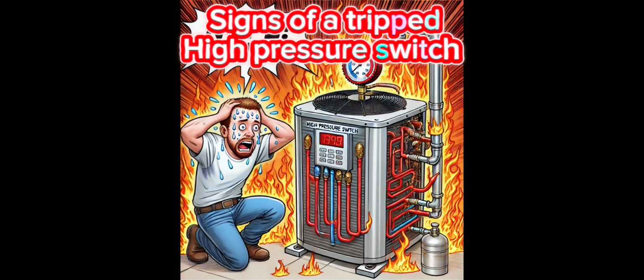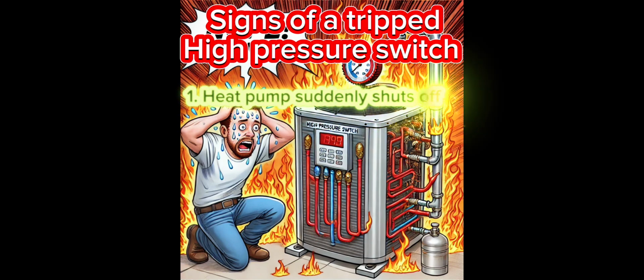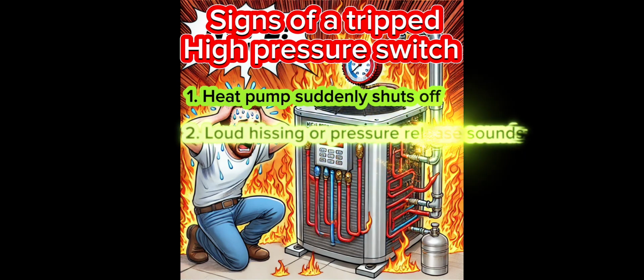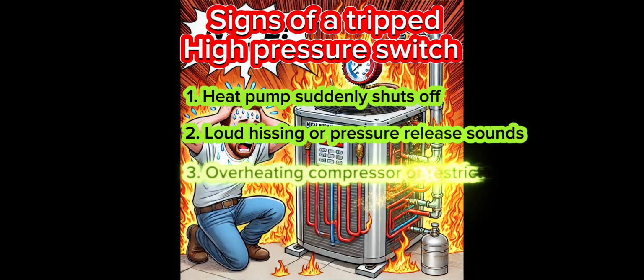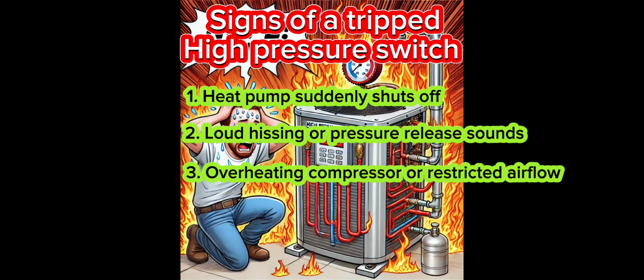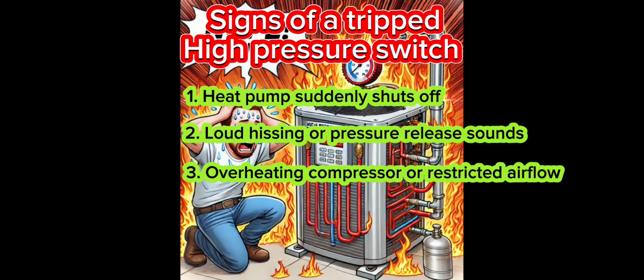The high pressure switch does the opposite. It shuts down the system if refrigerant pressure gets too high. This usually happens if the coils are dirty, airflow is blocked, or there's an overcharge of refrigerant. I posted a previous video where I went into detail about changing a high pressure switch. Watch that video if you need further assistance on that high pressure switch. The low pressure switch changes exactly the same.